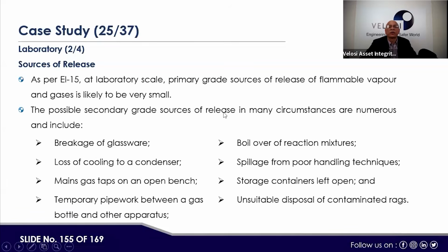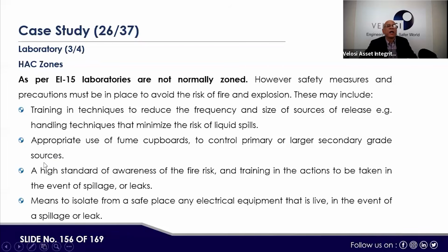The possible secondary grade sources of release in many circumstances are numerous, and include breakage of glassware, loss of cooling to a condenser, a main gas tap on an open bench, temporary pipework between a gas bottle and other apparatus, boil over of a reactive mixture, spillage from poor handling techniques, a storage container left open, and unsuitable disposal of contaminated rags. So, as per EI-15, laboratories are not normally zoned. However, safety measures and precautions must be in place to avoid the risk of fire and explosion.